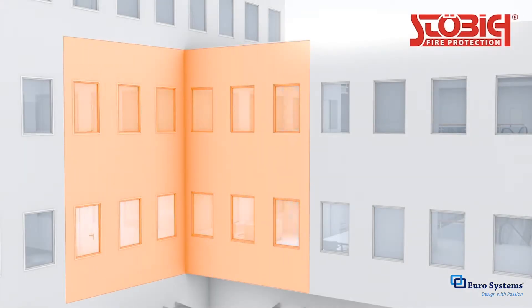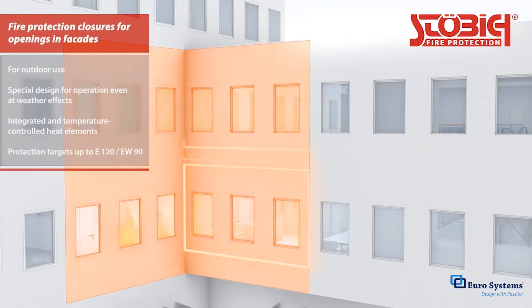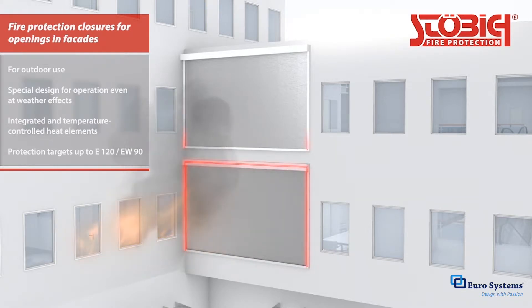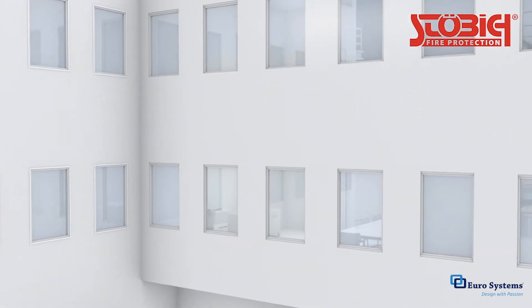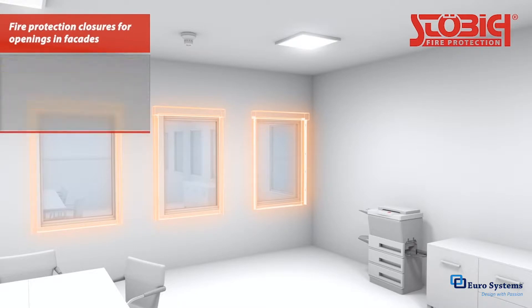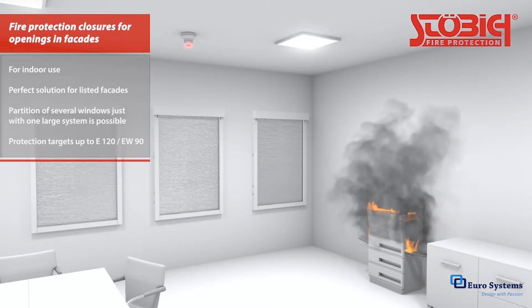The risk of fire spreading is particularly high in the corners of buildings. Fire protection curtains for facades are a good alternative to the more expensive option of insulating fire-resistant glazing. The special design and built-in heat elements ensure reliable closure even during inclement or cold weather. As an alternative to partitions or compartmentalization in outdoor areas, openings between walls can be closed off using concealed fire protection curtains. This is often a particularly beneficial option for the facades of historical buildings.